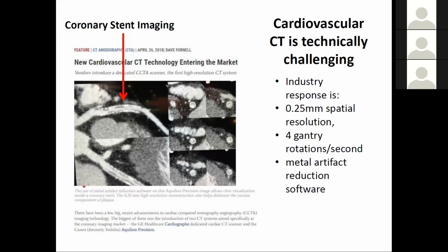You repair the sinogram by saying, okay, I don't like that there. Let me put something there that would be normal, like an extension, as in inpainting. Let me blank out that part, guess what might have been there from extension, from what's around it. And by the way, let me forward project and back project to inpaint there.